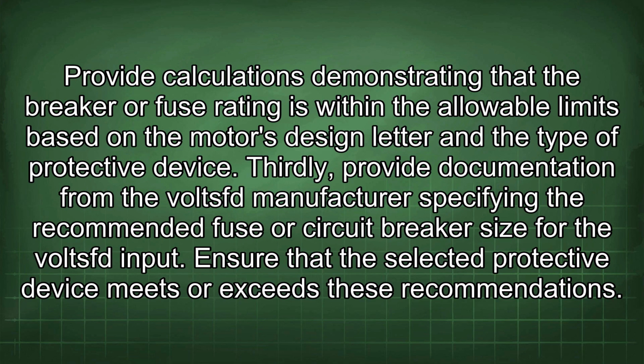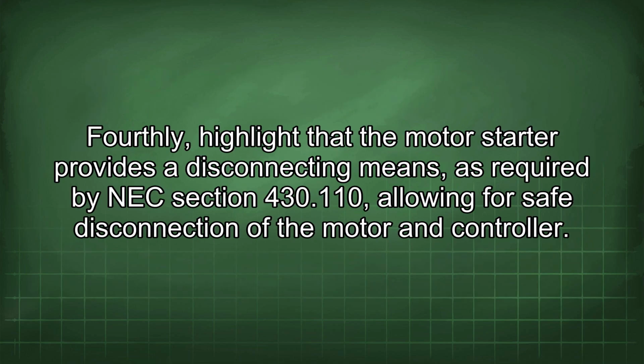Thirdly, provide documentation from the VFD manufacturer specifying the recommended fuse or circuit breaker size for the VFD input. Ensure that the selected protective device meets or exceeds these recommendations. Fourthly, highlight that the motor starter provides a disconnecting means as required by NEC section 430.110, allowing for safe disconnection of the motor and controller.